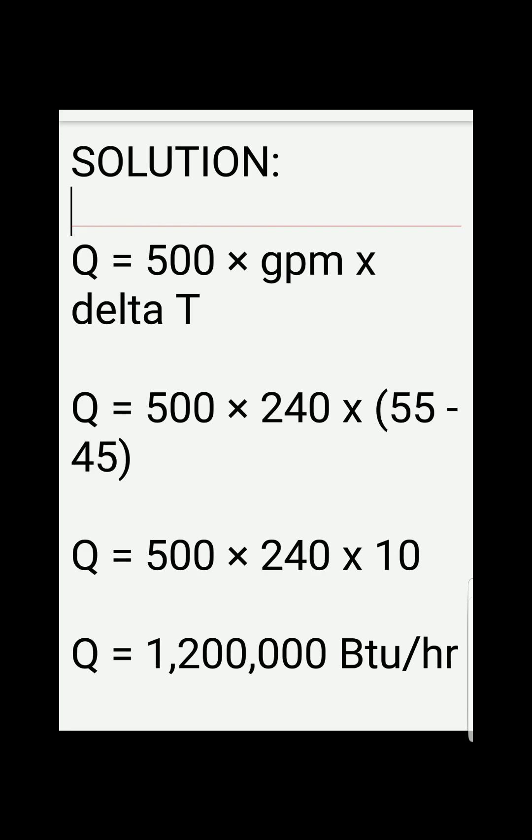We just need to substitute what we were given. For the GPM we have 240, and the delta T is the difference in temperature, which is 55 minus 45, or 10. Multiplying the three together, we get 1,200,000 BTU per hour.